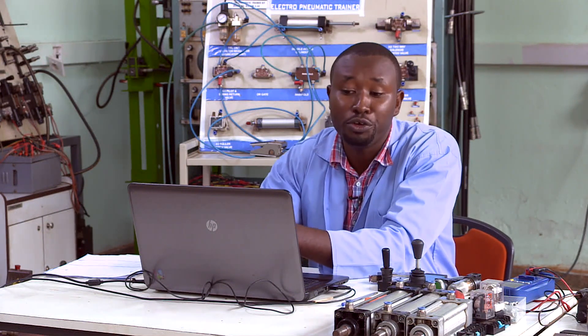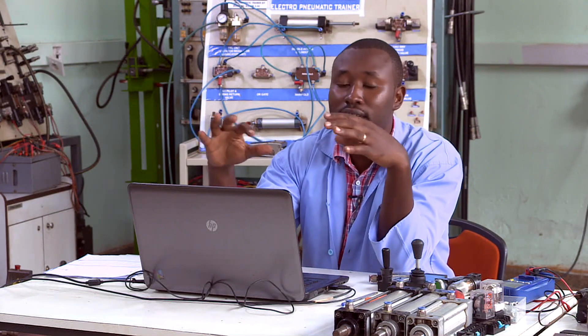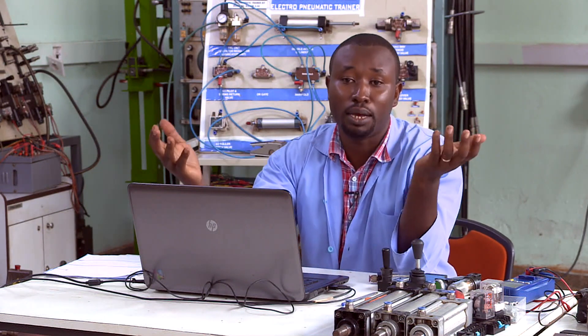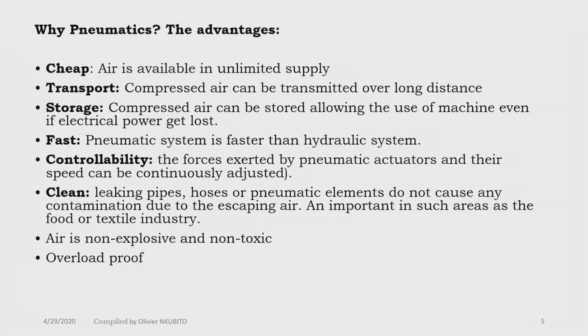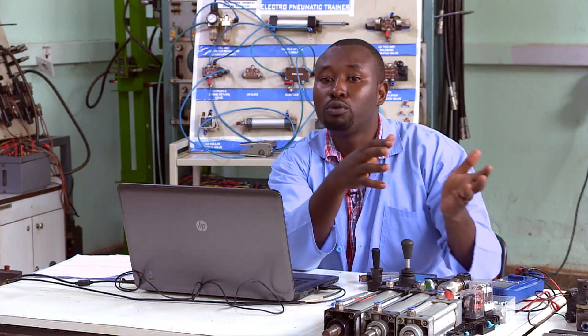Why do we prefer pneumatics? The advantages are: first, air is available and in unlimited supply. Second, air can be transported over long distances. Third, we can store air so we can keep working even if electrical power is lost. Pneumatics also works faster than hydraulics. Pneumatics is clean — unlike hydraulic oil — which means we can use it in textile or food industries. Pneumatics is also non-explosive, non-toxic, and has overload protection.